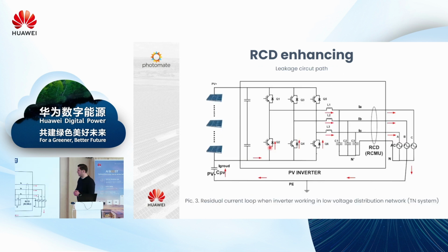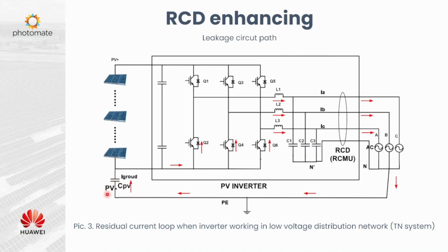So the path of discharging this capacitor goes like this - this is our capacitance, and it goes through the inverter to our network, to our grid. And here is very often your RCD breaker, which trips unnecessarily because of this current.